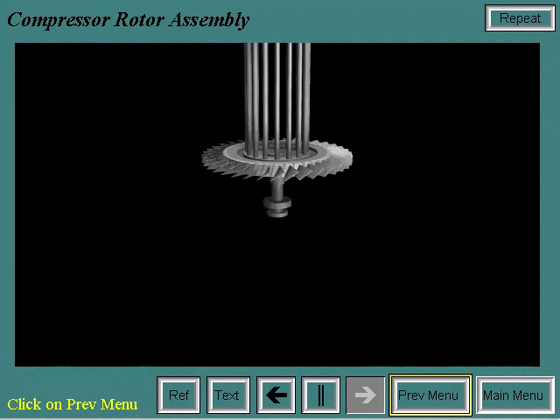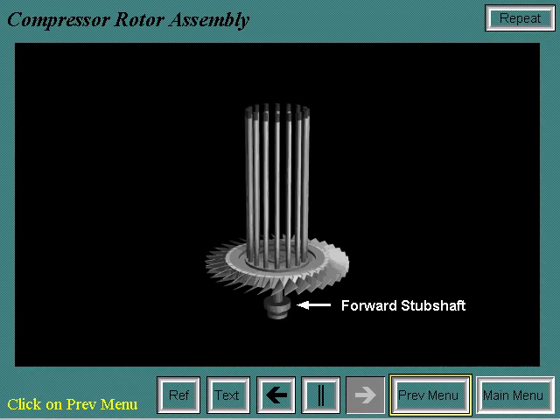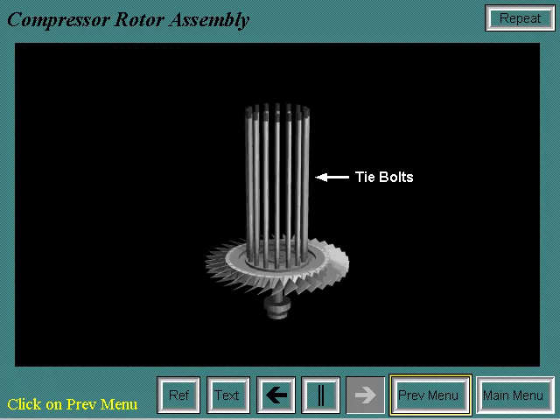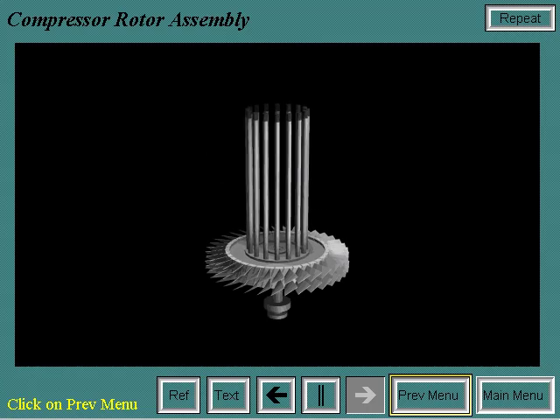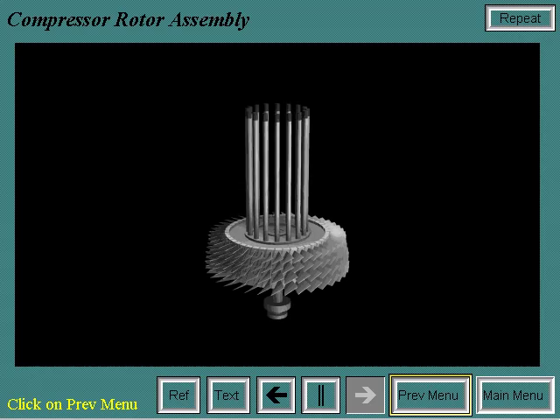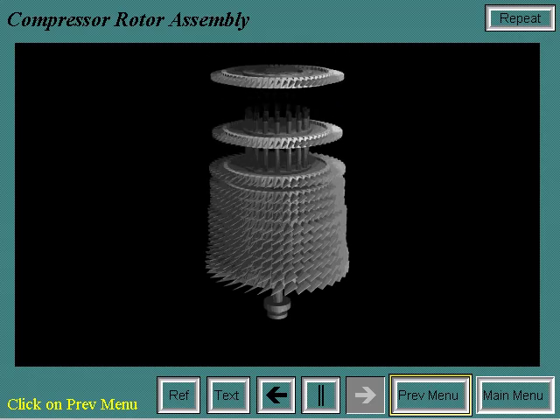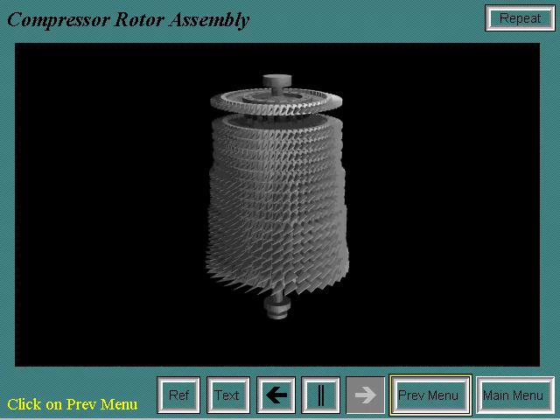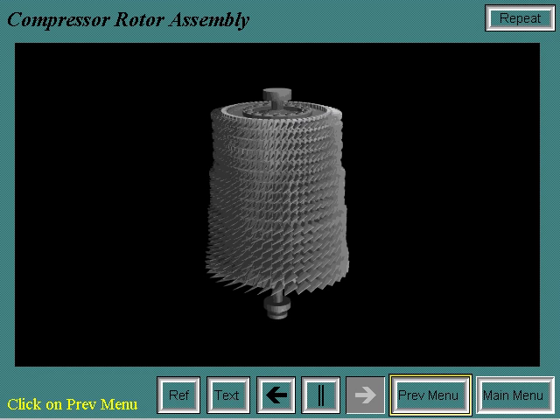The compressor rotor is assembled by vertically stacking the wheels. First, the compressor forward stub shaft and first wheel are put into the stacking pit with tie bolts in place. Then each wheel is slid vertically over the tie bolts. In the case of the MS7001EA, there are a total of 17 wheels on the compressor rotor. Once the last wheel and aft stub shaft are stacked, the tie bolts are then torqued.